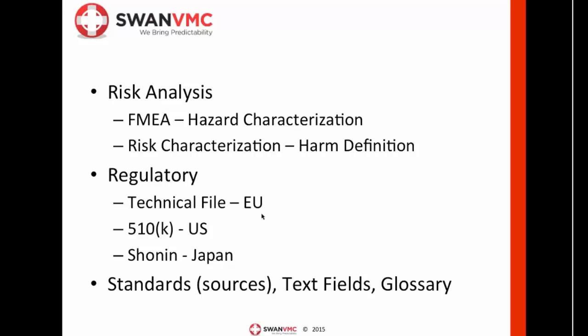And because of that, what we end up with is no lack of understanding of the expectations of the regulatory people late in the project, where they get all the engineering work and then say, well, you constructed this product requirements document improperly. Well, if the product requirements document is line 30 in the 510K and they're responsible for reviewing this as we go along, you don't get any surprises like that. So I really would recommend some thought about how the regulatory file and how we're going to process that as part of the project.